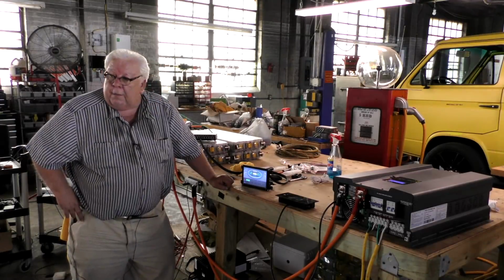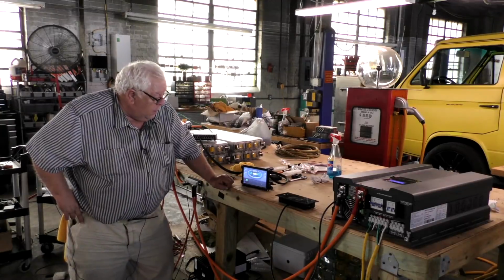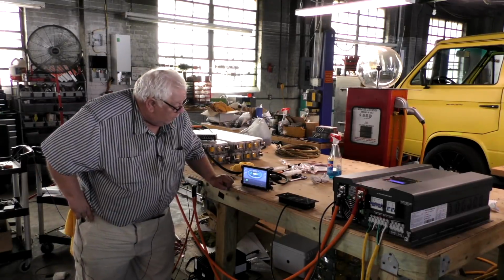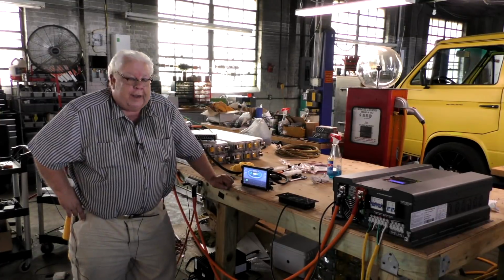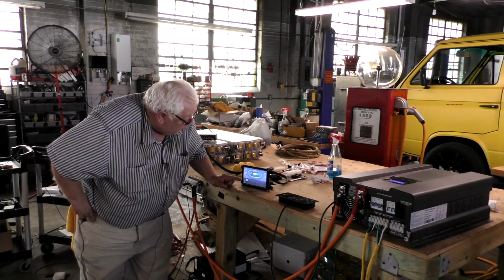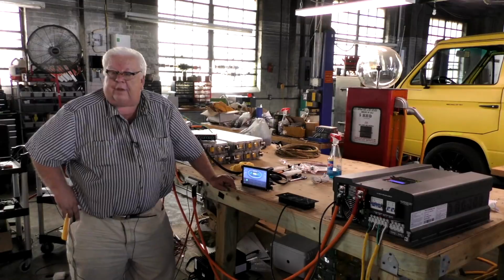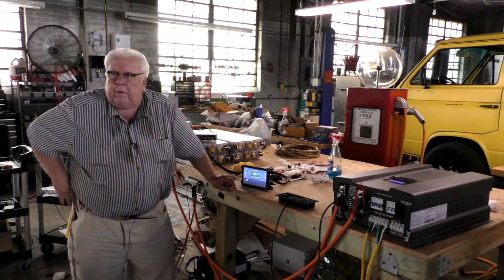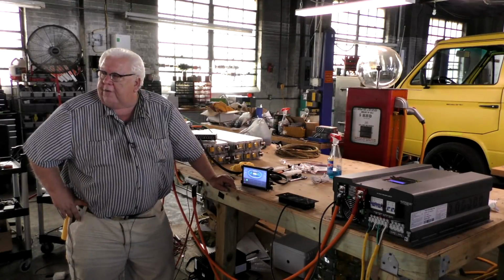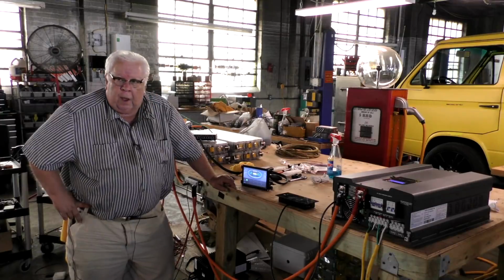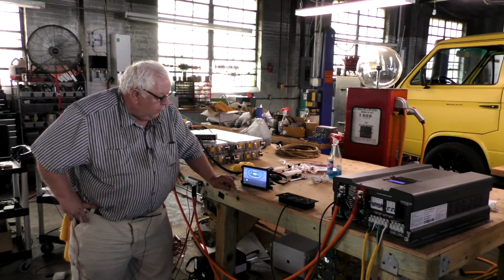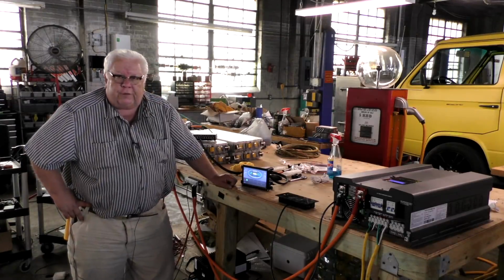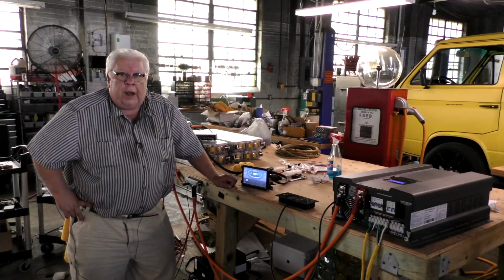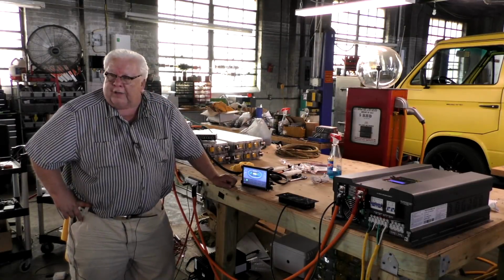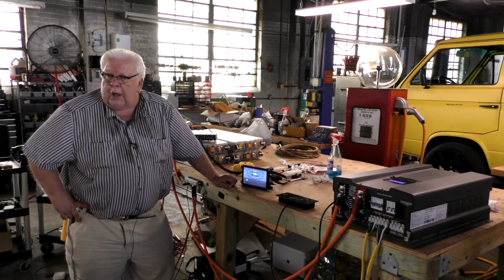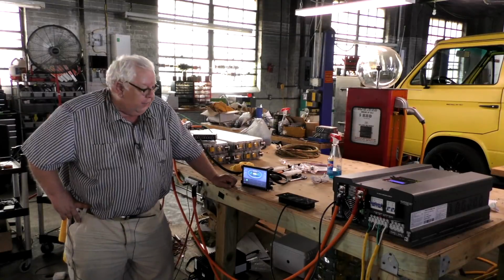Well, this is some dead air time. There it comes in, and now we have dropped at 5 minutes and 43 seconds, it looks like. Grid number 1 has synced in, and we've gone from 96 amps down to 38 amps. That's about 60 amps at 43 volts, and I would say that's about 2,500 watts. We just kicked in. So you can see that we're still discharging from the batteries at about 41 amps or 1,600 watts perhaps, and we're doing about 2,500 watts of our loads being handled by Solar Edge number 1.